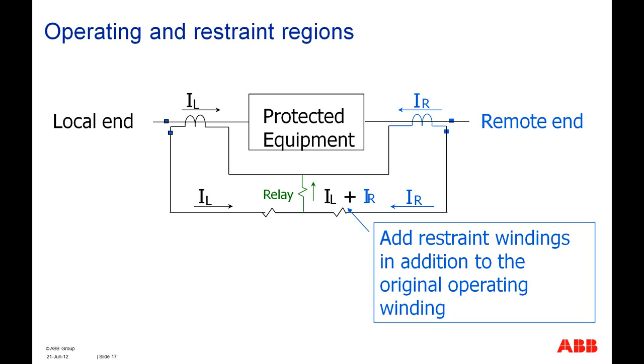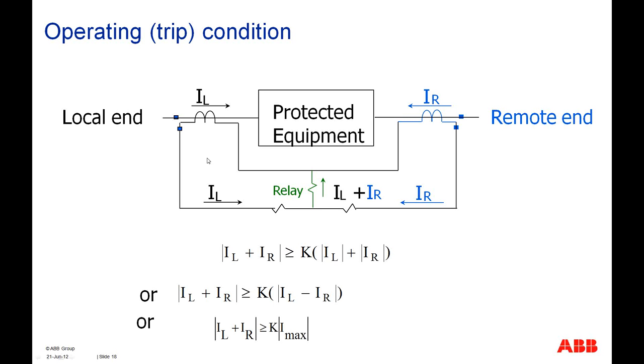Therefore, we have to introduce the restraining winding also into the differential scheme, which will provide more stability to the differential protection scheme. So we will have to add these two restraining coils into the circuit. In that case, the same differential current will flow through the operating coil, but there will be additional restraining currents, which will improve the stabilization. The tripping will occur only if the vectorial sum IL plus IR is greater than or equal to the absolute values of IL and IR together with the K factor. So K will determine the slope of the characteristics.